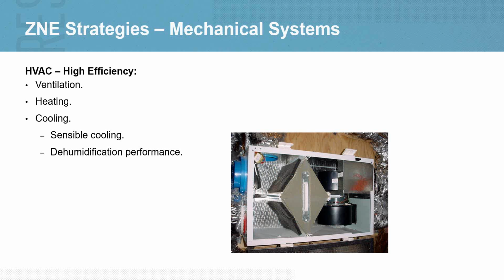The first thing I'll talk about is ventilation. From that last slide, you can see how well air sealed these homes are going to be, so it's no longer an extra credit idea to have a ventilation system—it's something we need to ensure there's enough fresh air coming into and out of the home, diluting pollutants and odors. This particular ventilation system is called a heat recovery ventilator. It pulls air into the home from outdoors while exhausting stale air from inside to outside, letting those two air streams cross in a heat exchanger so the fresh air coming in is tempered—not as cold in winter, not as hot in summer. So ventilation is really important.